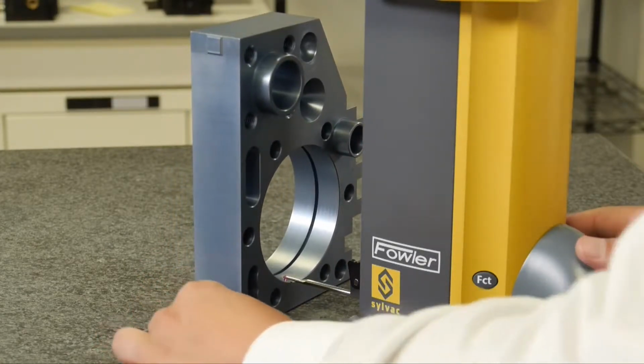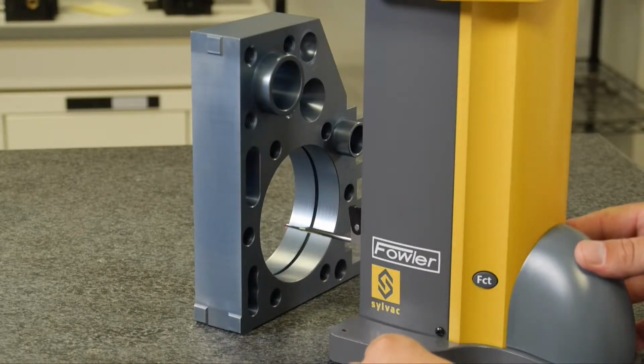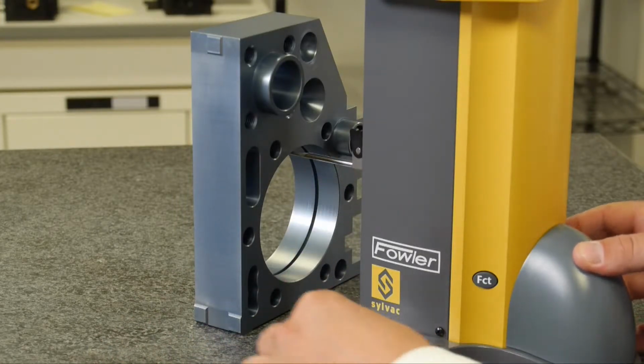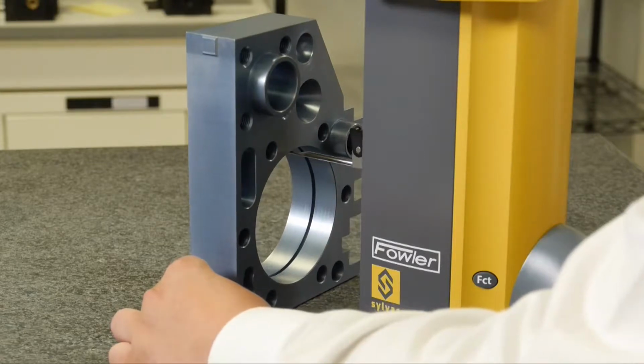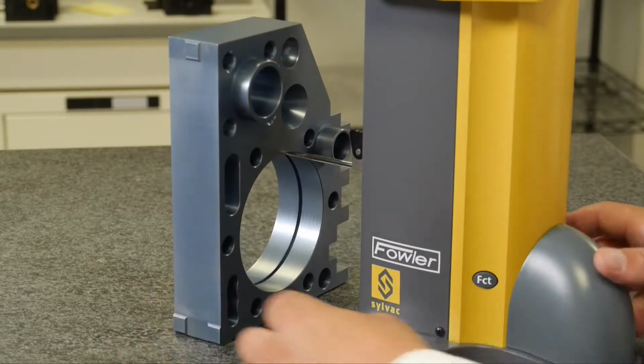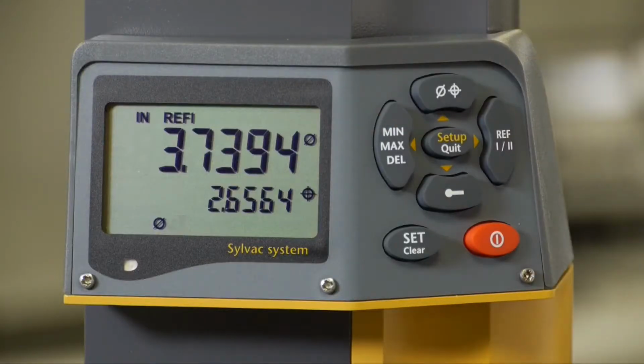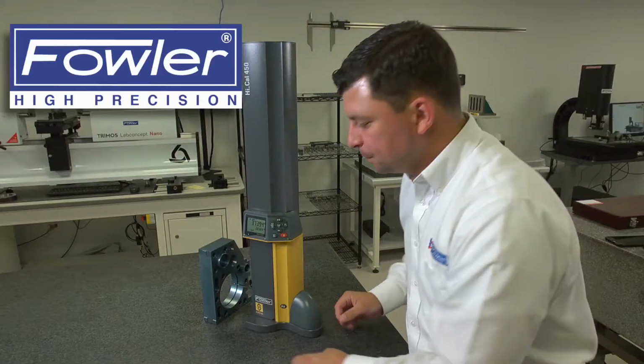I can then drive up to the opposite side, engage my probe, sweep it back through, and once I cross the reversal point, my display will freeze, locking in on my diameter and my center line. My center line is currently based off of the 0 position established on my surface plate.